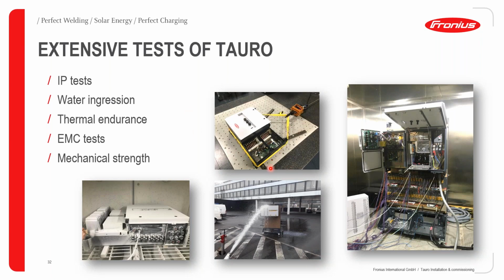We've also taken the Tauro and done quite a few mechanical strength tests. If you look at this picture on the right, you can see we have a whole lot of cables connected in. We basically connected every DC string onto the Tauro and connected the AC cabling, and this is what we call the electrical endurance test. This will ensure that even if we put the maximum current per string, the inverter is still able to function properly without anything tripping or starting to smoke or anything to that effect.